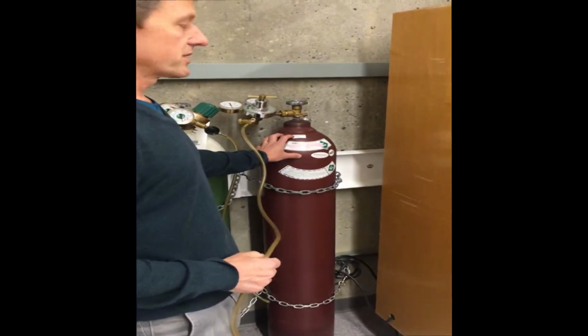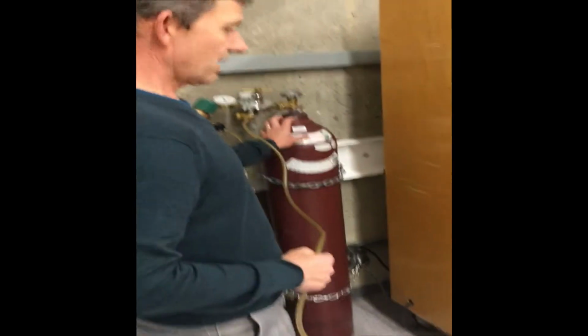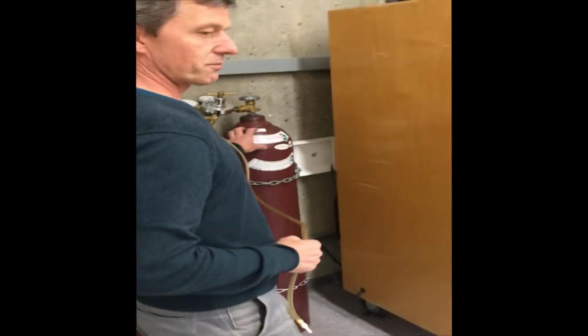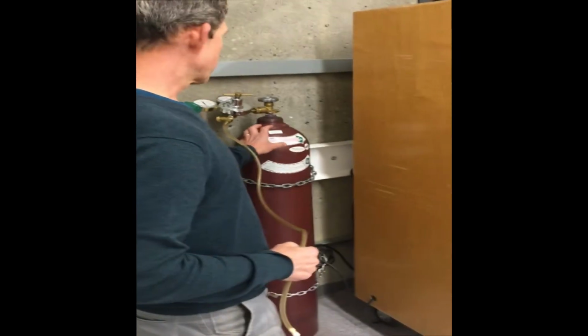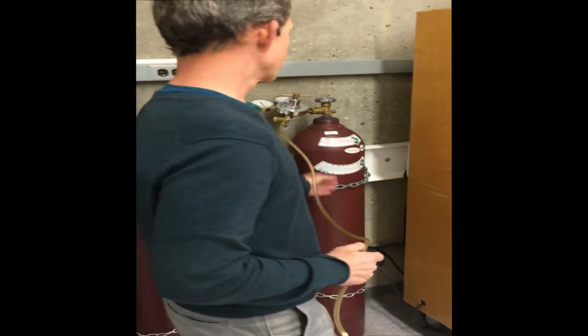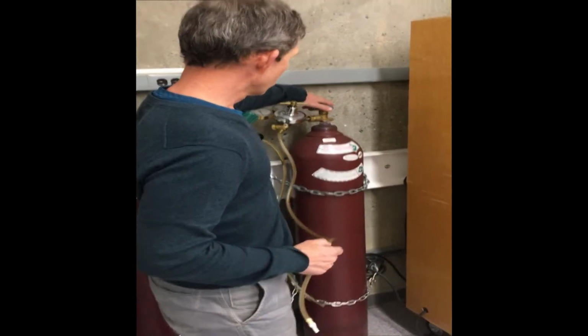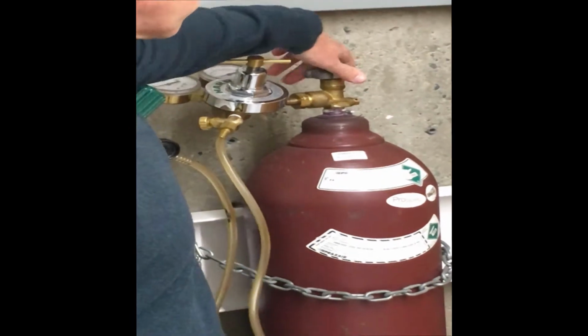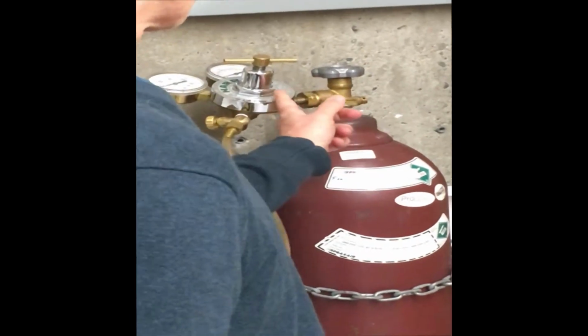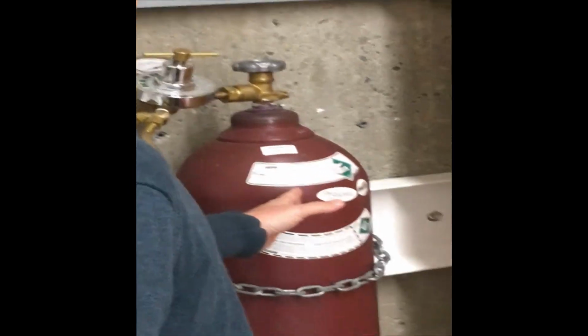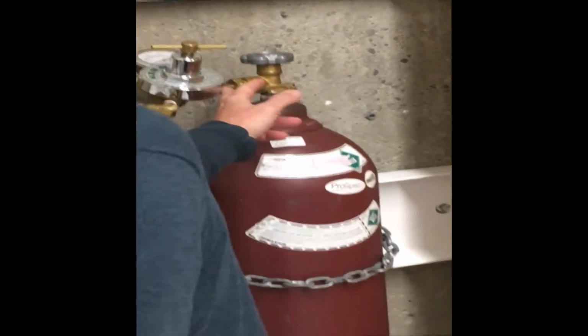So in order to do that, what we have here is a large cylinder that has calibration gas in it. You have to keep in mind that this is under a tremendous amount of pressure. So there's a 2-valve system to open this up. The first larger valve will open up the gas so that the gas can go from the cylinder into the regulator. So this can be as high as 2,500 pounds per square inch.